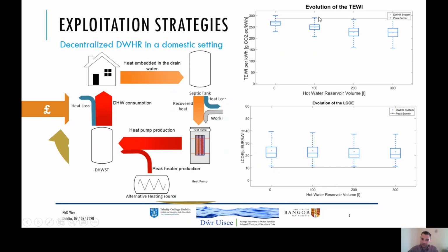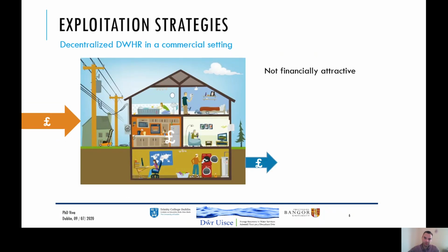However, on the cost side of things, the results are not as promising, since we have a life cycle cost of about 130% higher than the traditional heating system here, represented by the gray line. You can see that over the different sizes of the storage tank, the life cycle cost doesn't vary that much. That's because the capital expenses form the bulk of this life cycle cost, and the savings in operational expenses don't counteract this.